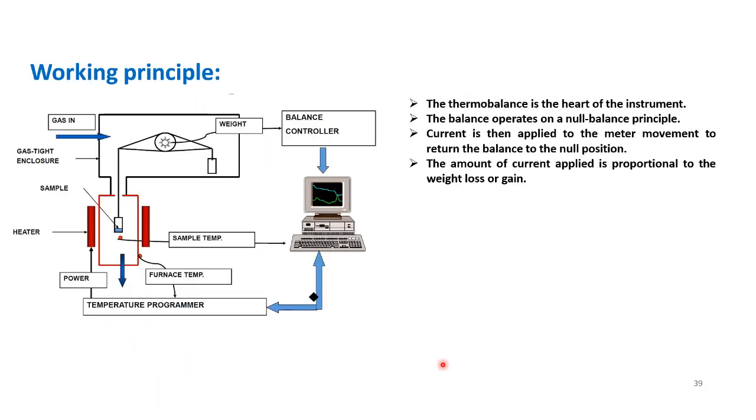So the principle here: we have a thermobalance. On one side we keep a sample, and on the other side, to balance it, we have another weight. It is connected to a controller, and the mass of this sample will come directly to the computer screen. So when we load the sample, the thermobalance will measure the mass of the sample, and it will show on our computer screen.